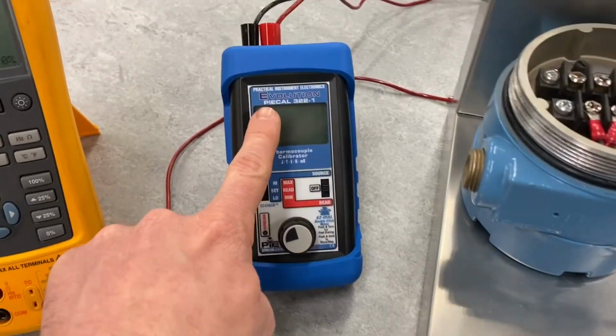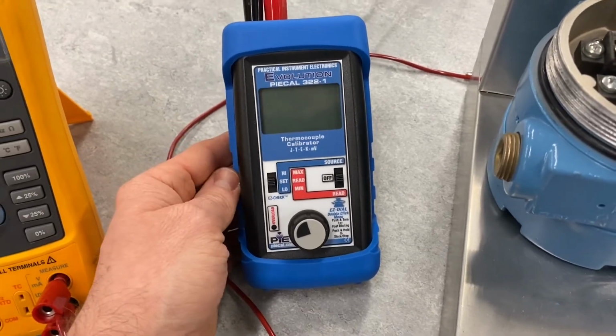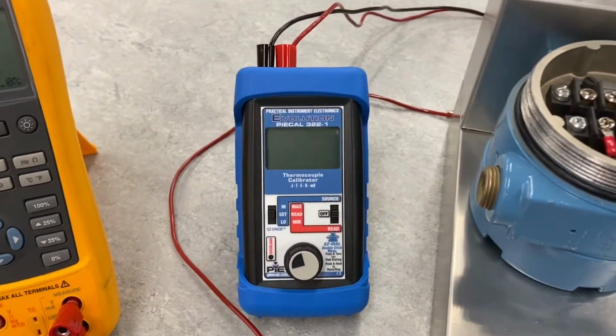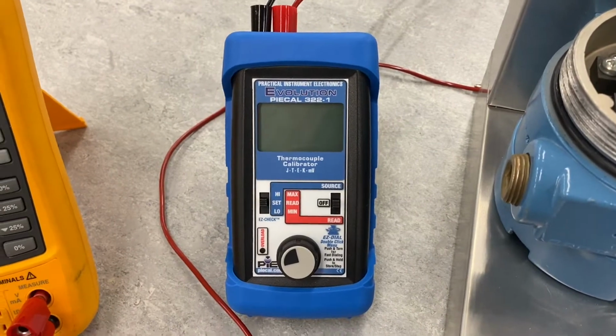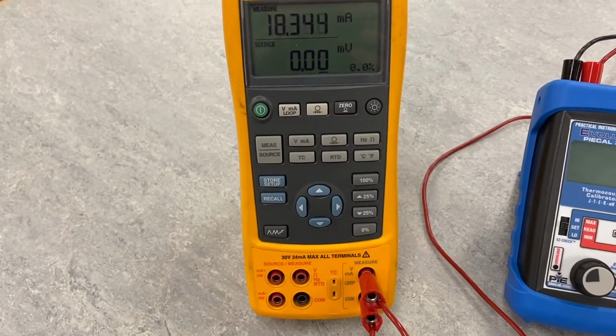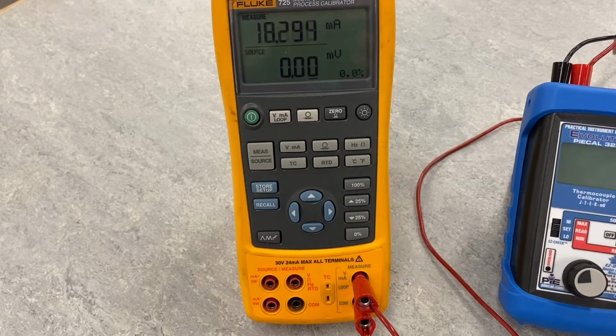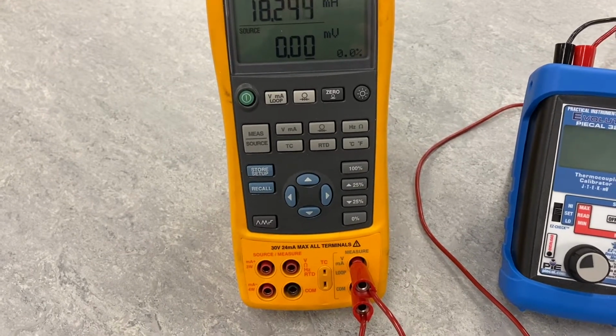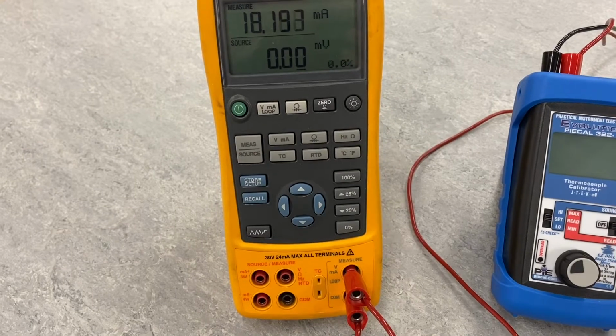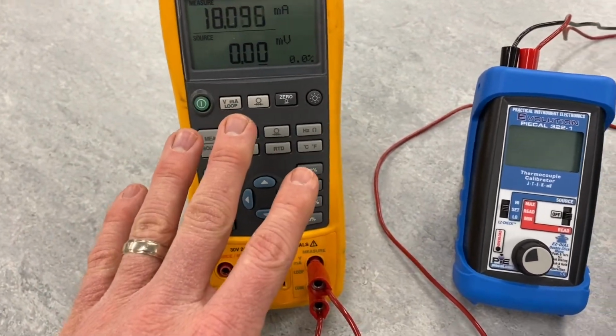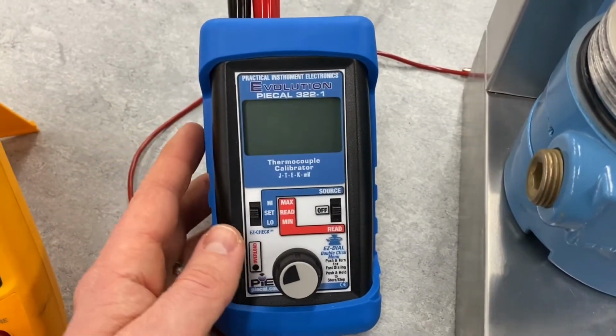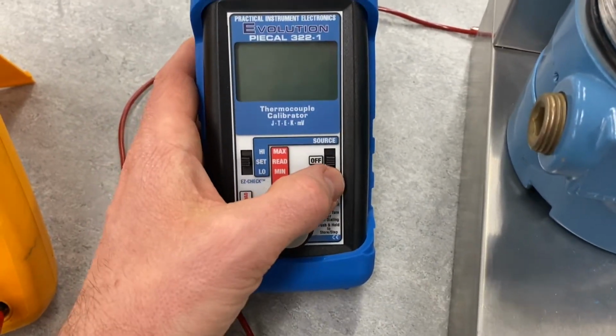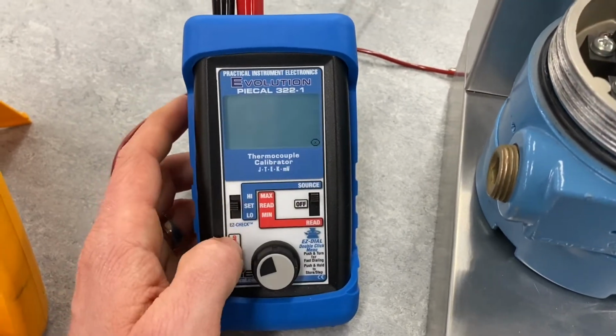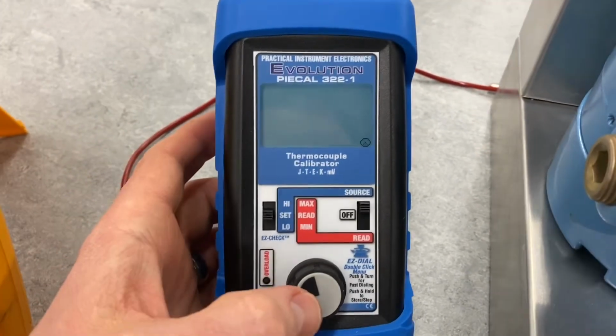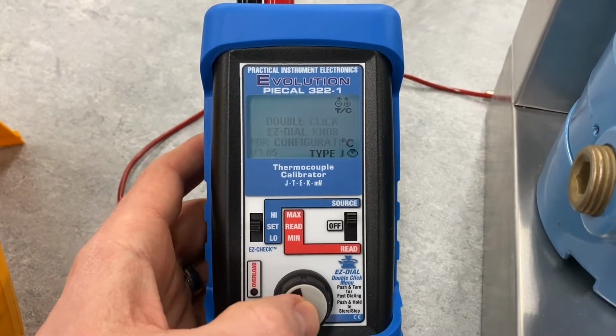All right, so this time around we're going to be using a thermocouple calibrator. This is a device that's designed for calibrating thermocouples. It's specifically only for thermocouples, whereas our meter over here can do more than just thermocouples. It can do RTDs, and it can be used for measuring current, measuring voltage, sourcing current. So it has a broader application, whereas this is specifically for thermocouples only. So what we're going to do is power this on by pushing this button up, and the next step is it's going to ask us to double click this knob.